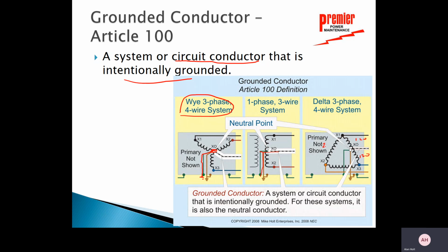120 here, 240 here, 240 here, I wouldn't go from neutral to this side. That's the high leg, the X2 is. But I do have a ground. This is my neutral for my 120 volt lighting inside that facility, and it goes to ground. So a grounded conductor is a system or circuit conductor that is intentionally grounded. For these systems, it also is the neutral conductor in every example that I've shown there. So understand the difference between a grounding conductor and a grounded conductor. The grounding conductor is the actual conductor going to ground.